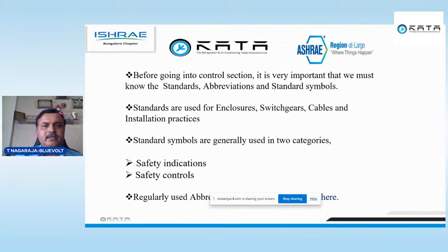So before going deep, we can once again refresh standards, abbreviations, and symbols. The standard symbols are generally used for only two categories, that is safety indications and safety controls. Safety indication shows whether our machine is running in a safe condition or abnormal condition, whether an alarm is present or not. What are the safety controls? If my AHU is running, then only my valve should open. These are typical safety controls. If my HP/LP is all right, then my compressor should run. If every interlock is closed, then only I should start the machine. So these are all the controls.